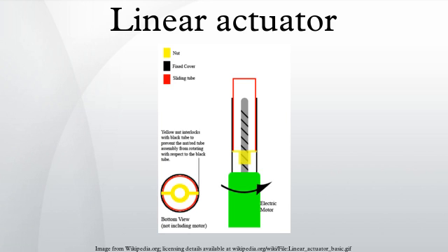The direction of motion of the nut depends on the direction of rotation of the lead screw. By connecting linkages to the nut, the motion can be converted to usable linear displacement. Most current actuators are built for high speed, high force, or a compromise between the two. When considering an actuator for a particular application, the most important specifications are typically travel, speed, force, accuracy, and lifetime.